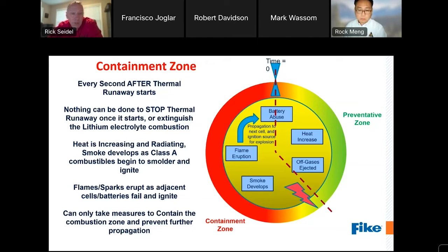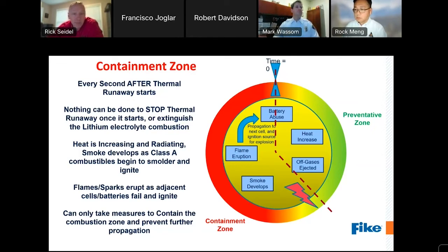During thermal runaway, you will likely witness sparks and flame erupting from the runaway cells, which result in very intense and increasing radiating heat and smoke as adjacent cells much more quickly enter thermal runaway from the intensely propagating heat, thus presenting a spiraling hazard that can quickly get out of control and keep the clock spinning round and round. It's very important to try to stay out of the containment zone if at all possible, and the only way to do that is by making sure you have detection or monitoring in place to notice and recognize the sequence of events that will occur in the preventative zone.